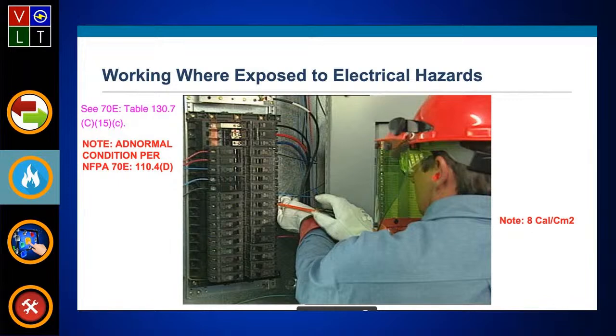This is what the code requires, 110.4D, showing an abnormal condition. By the code, if you stand in that limited approach boundary, you need a sock hood or balaclava. He's dressed up enough for what he's doing based on the calorie rating, but if he should be standing in that limited approach boundary, he'd need that sock hood on. This is abnormal because he's gaining access to energized conductors and circuit parts, so you have to dress up for that.